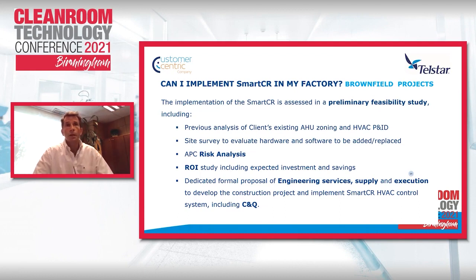Now, in a brownfield, it will require a preliminary feasibility study before taking decision to go further or not, because we may face situations where the changes in the HVAC system, air ducting or even air handling units are major, and that will require investment or shutdowns that you are not planning with. So we need to make a preliminary feasibility study of the installation, data acquired, and survey of the current installations, but also the hardware and software. We may have to adapt also the BMS or EMS or even the PLCs of the existing facilities.